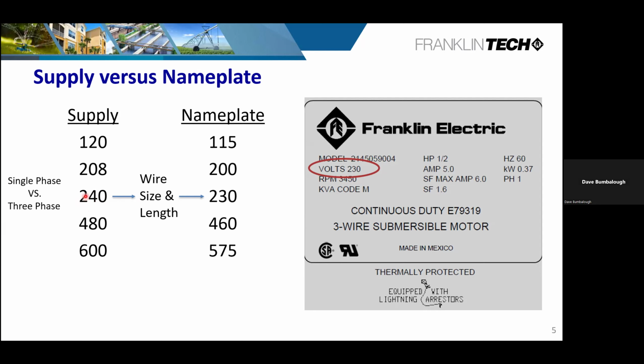For those of you that don't know, most of our equipment we try to nameplate about 5% under that. If voltages start drifting too far, you can cause issues with motors burning out and problems with the wire. That just opens up Pandora's box for all kinds of issues. So going forward, we as contractors, especially on the water well side of the business, have to pay more attention to this because the equipment is not changing.